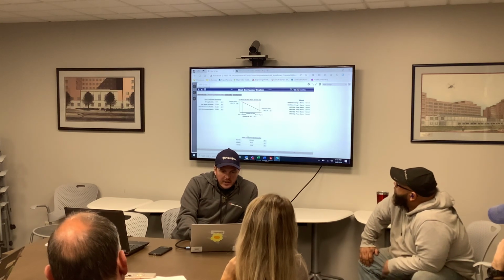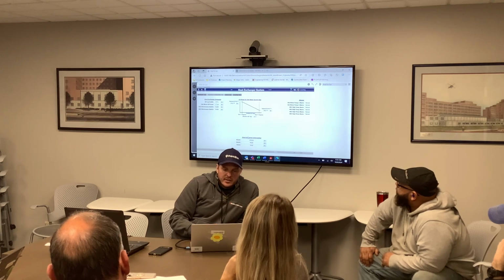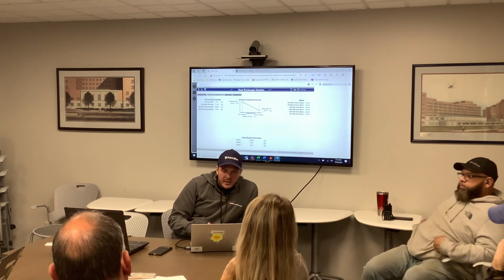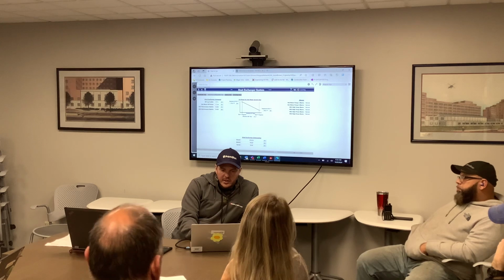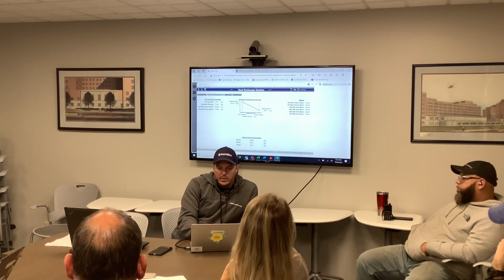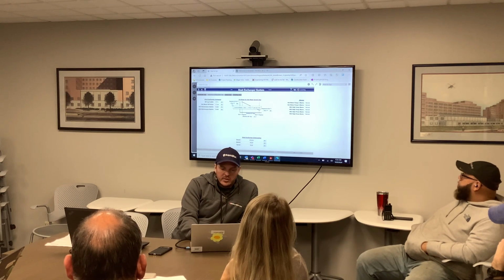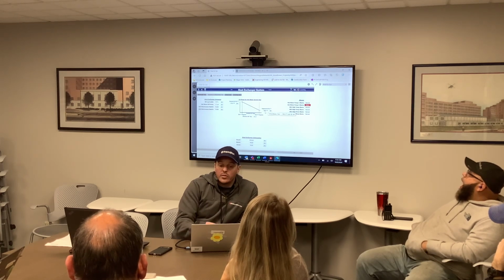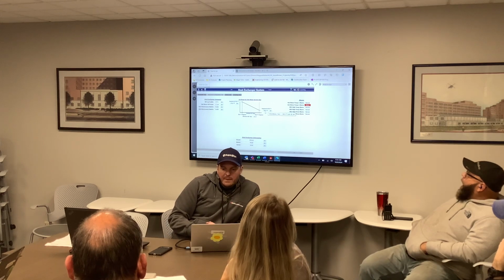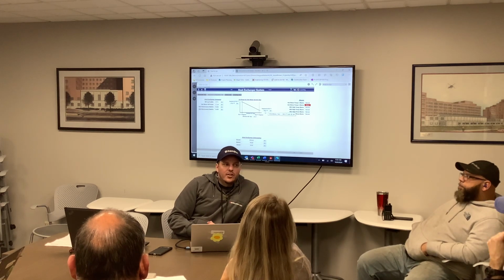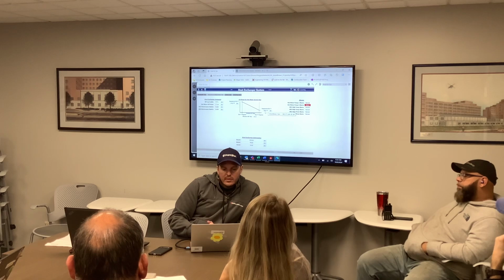So under here, we have our hot water reset based on OAT, similar to the air handler's DAT reset. At 30 degrees or below, it's going to modulate to 170 degrees, and at 65 or above, it's going to go to 140. So right now, the pump went off. Yeah, it's in hand.